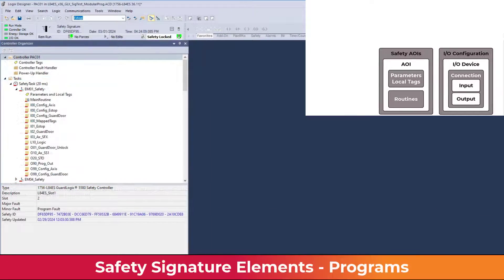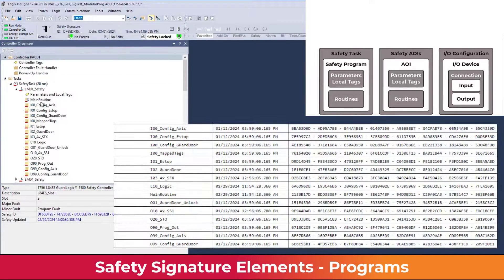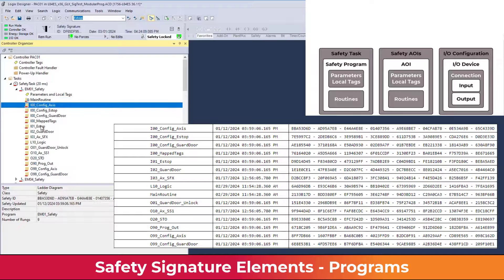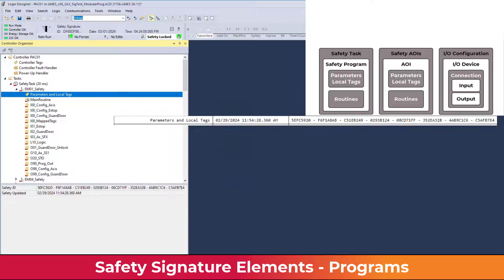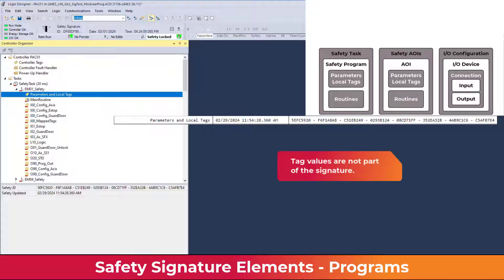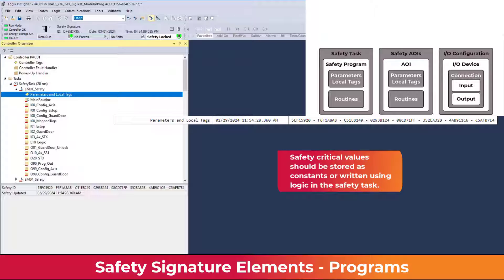Safety programs have a signature for each routine and a signature for parameters and local tags. Changes to parameter and tag properties — including name, type, and structure — are monitored by the parameters and tags signature. The value of a tag is not part of the signature unless the tag is declared a constant.